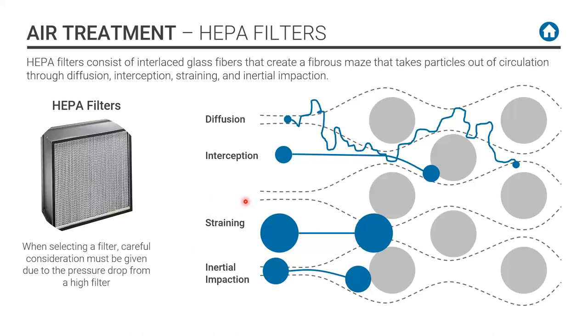So let's talk about how a filter works, whether it's a HEPA filter, which we'll talk about, or a standard filter. A filter is really a bunch of glass fibers or fibrous materials that are meshed together that capture particles. So large particles are caught, smaller particles may be a little more active. And we're going to talk a little bit about diffusion. The reason I bring this up is you'll see on one of the slides that you would assume the denser the filter, the more it captures, which is true. But when you get very, very small particles, there's something called Brownian motion. I'm sure many of you know better than me, because I haven't studied that since college. Something is so light, it becomes so erratic the way it flows that the particles have a very, very diffuse passage, and the smaller particles can get caught, whereas an intercepted particle, a heavier particle, might get right through.